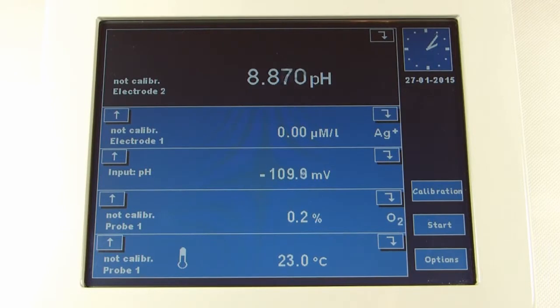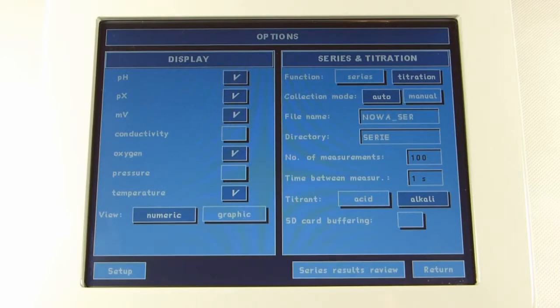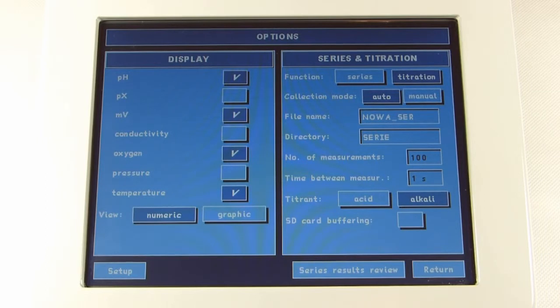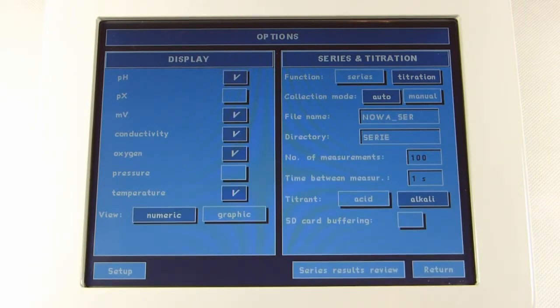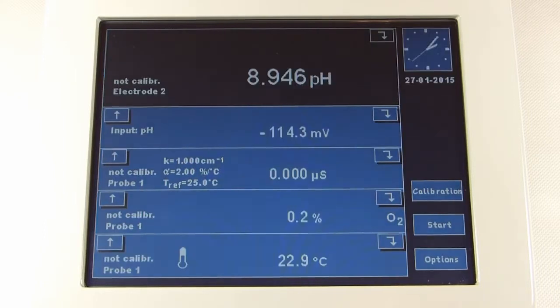To change the function displayed on the measurement screen, press the Option button. And in the display window, choose the function by pressing the appropriate button. We choose the conductivity measurement instead of the ion selective measurement. To do so, press the PX button. The marker next to the button disappears. Next, press the conductivity button. The marker next to the button confirms choosing this function. Measuring mode.